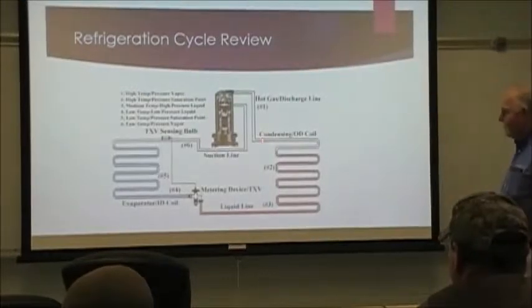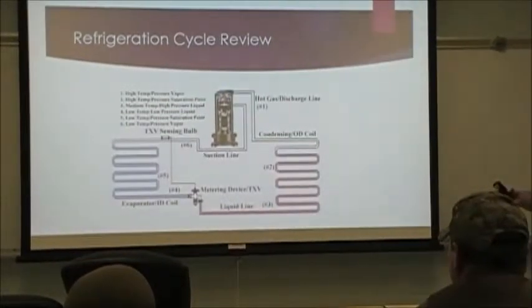It comes out as high pressure vapor, goes into the condenser, rejects its heat, goes to the metering device where it converts it to a low pressure liquid and vapor mixture, then goes to the evaporator and absorbs heat there completely until it is 100% vapor - it's supposed to be 100% vapor. When it comes out, it comes back to the compressor as low pressure vapor.